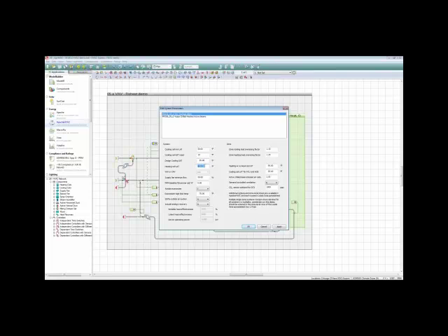And I'm also assuming that in dehumidification, I might be driving the off-coil temperature of the cooling coil down to 50, but I'm going to immediately warm that up to 54 before it leaves the air handler. And this will never go below 54 in the case of resetting the cooling coil temperature downward for the purpose of space conditioning. In other words, for meeting loads as opposed to dehumidification, these coils won't fight each other.